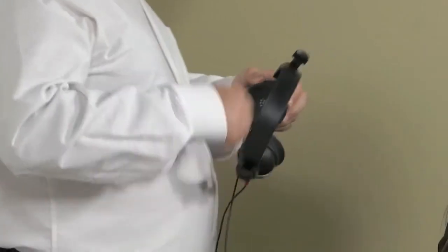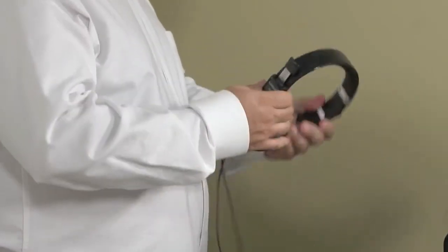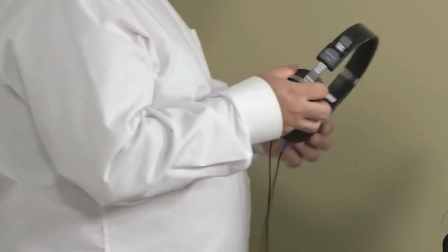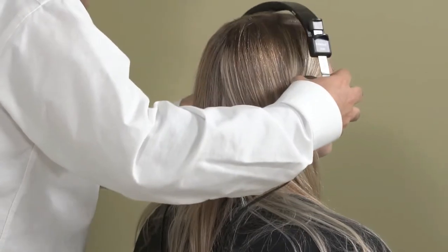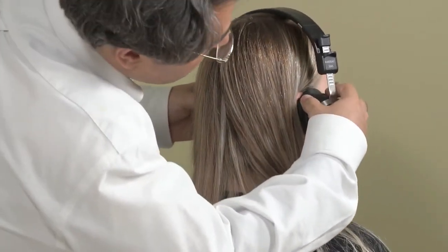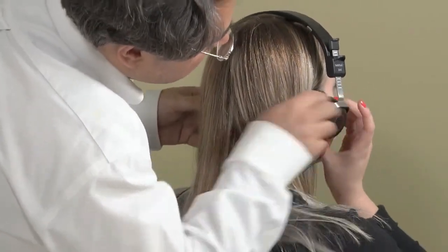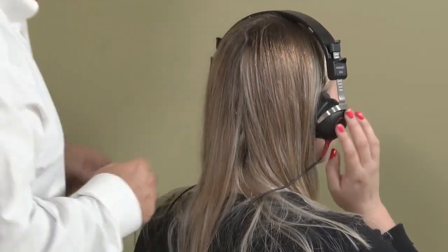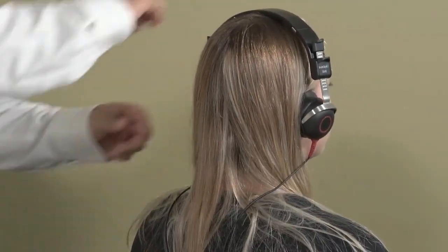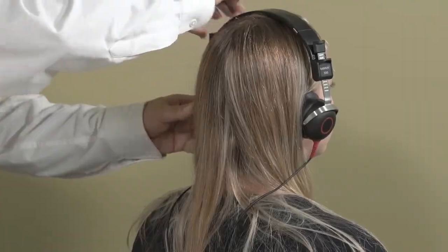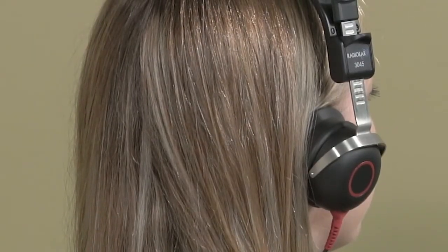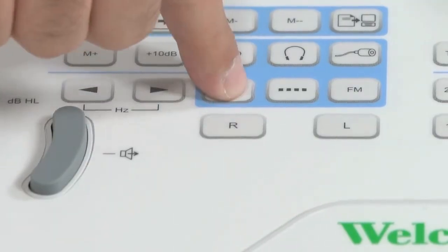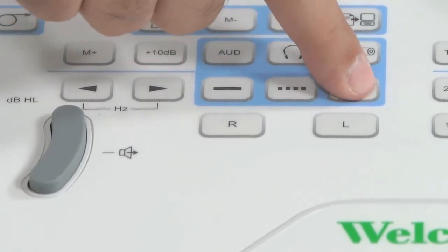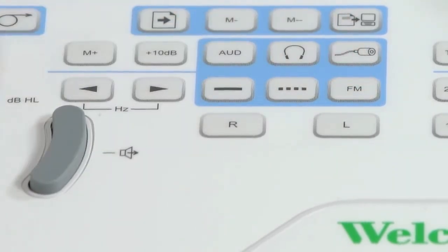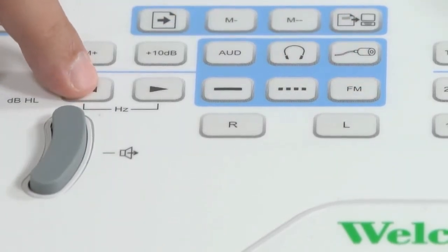Adjust the headband so that it rests solidly on the crown of the patient's head and exerts firm pressure on both ears. Center the headphones carefully over the ears. Make sure the diaphragm of the earphone is across from the ear canal opening. The earphone with the red connector goes on the right ear. Next, select the desired tone type: steady, pulsed, or frequency modulation. The frequency buttons help you increase and decrease the frequency you are presenting.